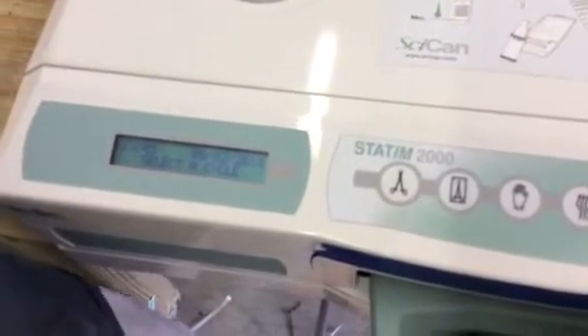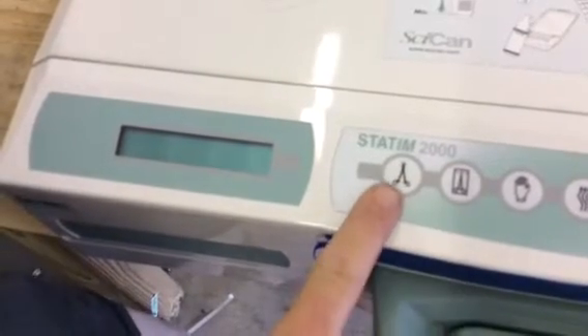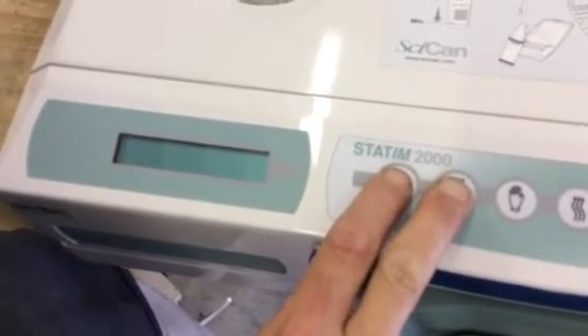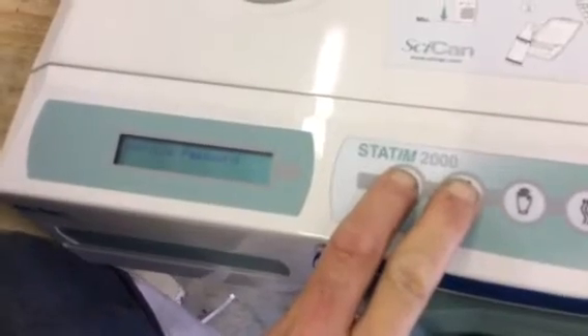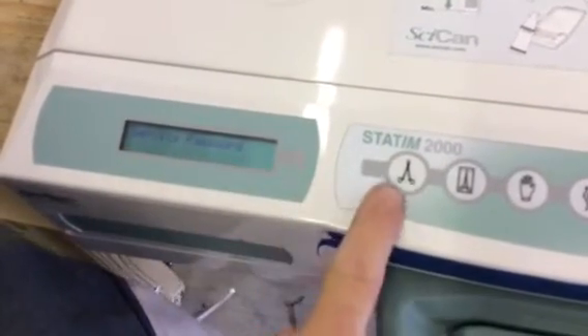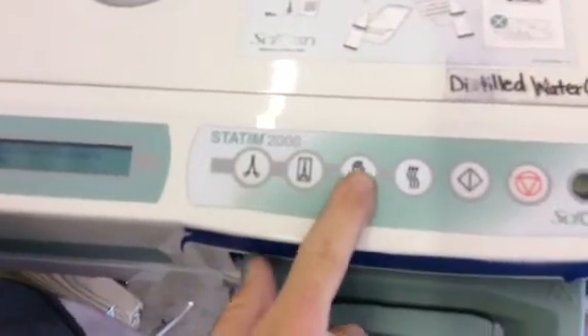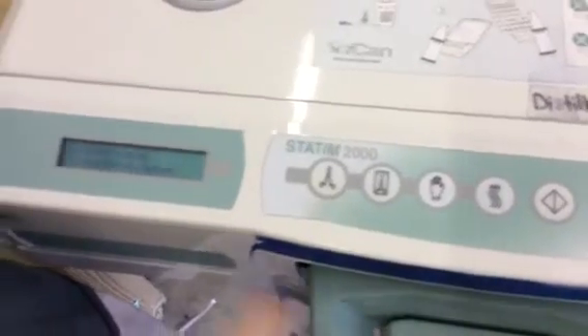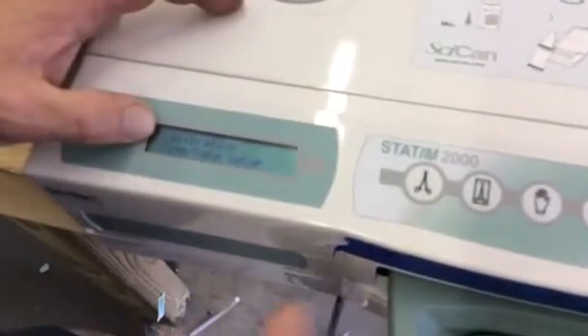So I'm going to turn the machine back off. I'm going to hold down the unwrapped and the wrapped buttons, and then I'm going to turn the power switch on. See service password. It's unwrapped, wrapped, glove, stop. Now you can see that the arrow is next to calibration.